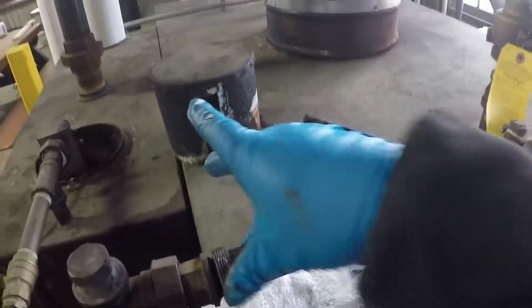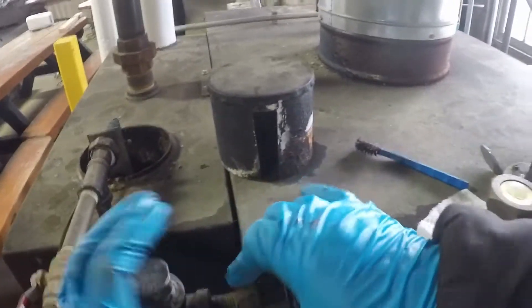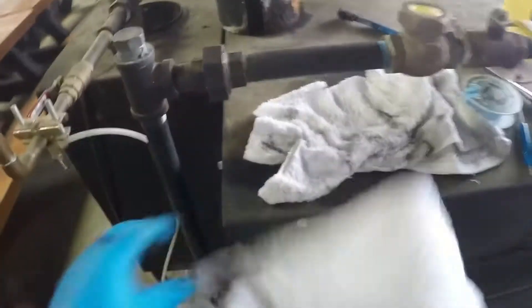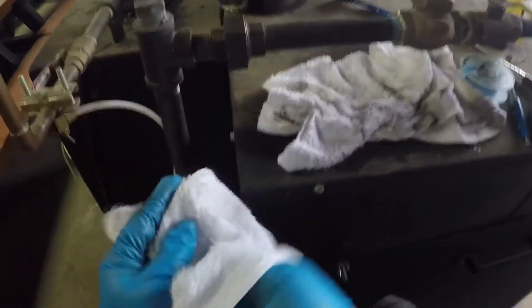Don't be trying to put your anti-seize inside your boiler. You will take a risk with your water quality and possibly develop turbulence, erratic low water trips, and horribly inconvenient problems.